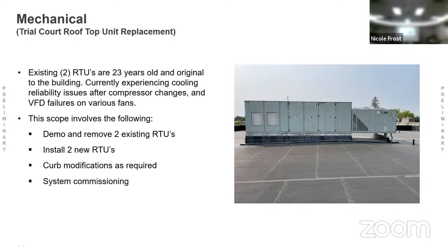You said all new controls, help me understand what you mean. That building is a bit different than this one. This one is 1970s pneumatic, essentially, while that one was done in 2000 with digital controls. So this building will be getting all new wiring throughout the hallways, down to every thermostat, box, unit, and boiler, because it never existed. That building already has the wiring in place, so we're just replacing the devices, like the thermostats and the computer-like panels in the mechanical rooms that are tied to the boilers and rooftops. Those we put in place.